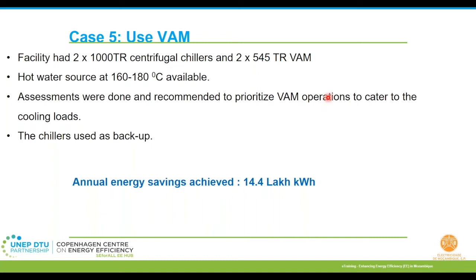What happened was the facility was giving priority to the centrifugal chillers first, and if the cooling load was still required, there was a demand, then the VAM machines would run as a backup. But during the study, we saw that a good amount of heat was being wasted, and the heat source was easily at around 160 to 180 degrees centigrade. So it was a simple switch in process, wherein we asked them to give primary preference to the VAM machines to cater to the cooling loads. And if you still require some more cooling, then you can call in the centrifugal chillers.